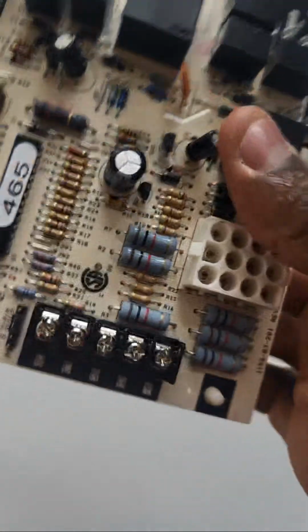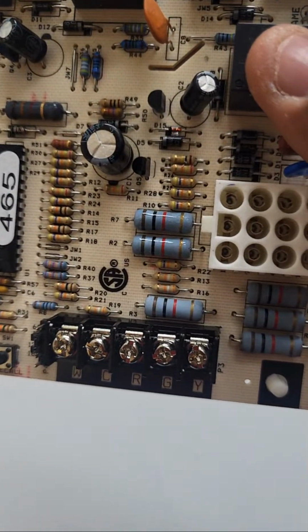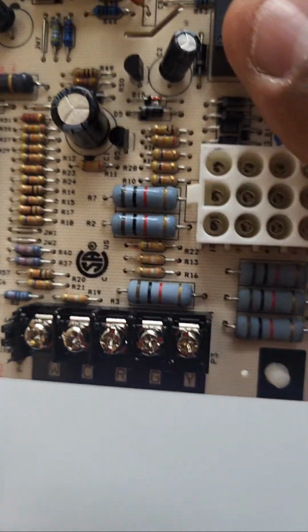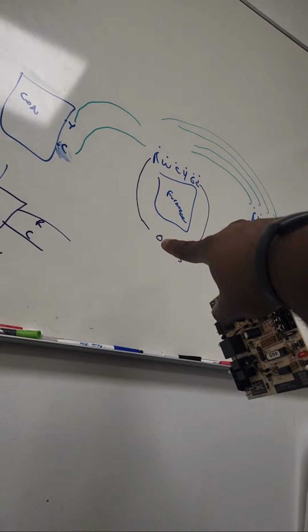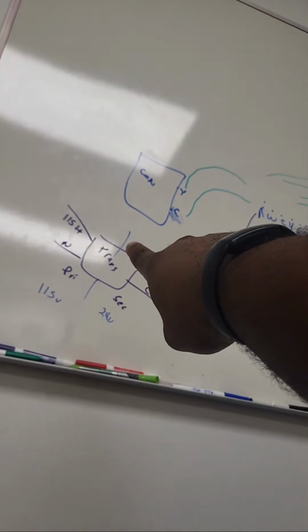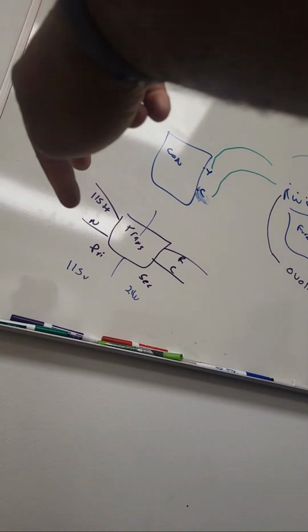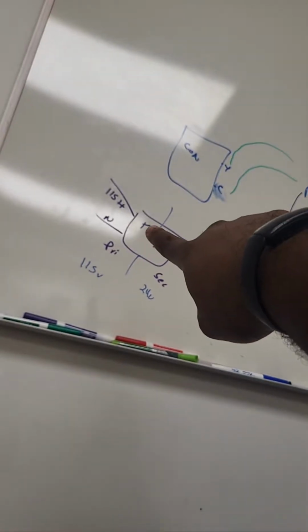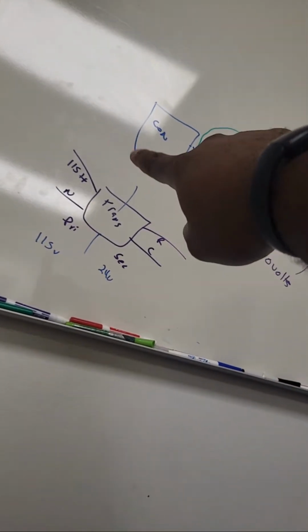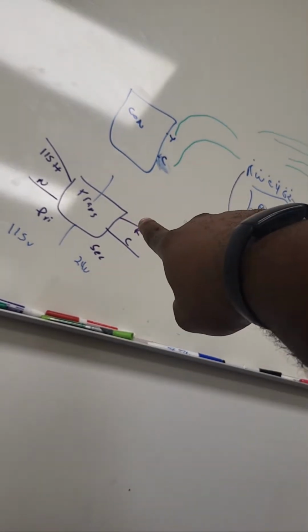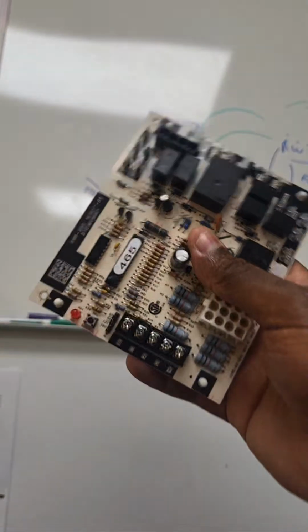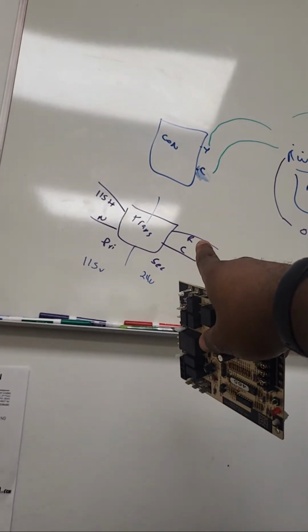So that transformer is going to send 24 volts from R to C. Now guys, here's the thing, back to what I said: I had 0 volts from R to C. So the first thing I did, knowing what I just told you guys, was know that my transformer's purpose was to step power down. In this scenario, I had 115 on my hot side between my 115 and ground, so I knew power was getting to this transformer. But what I did was check for 24 from R to C, leaving the transformer, and I had 24 volts.